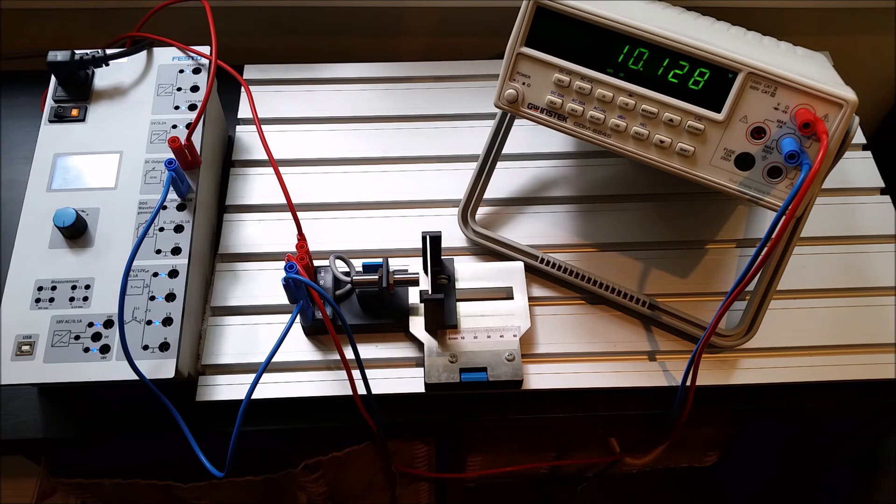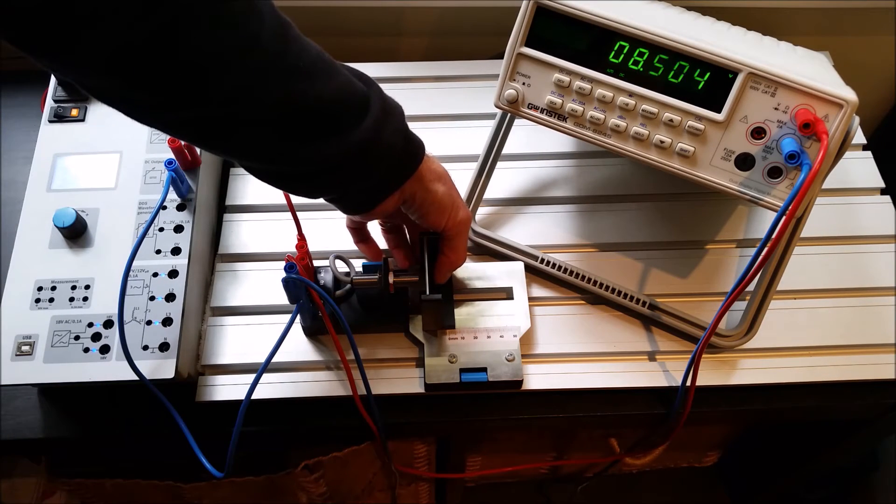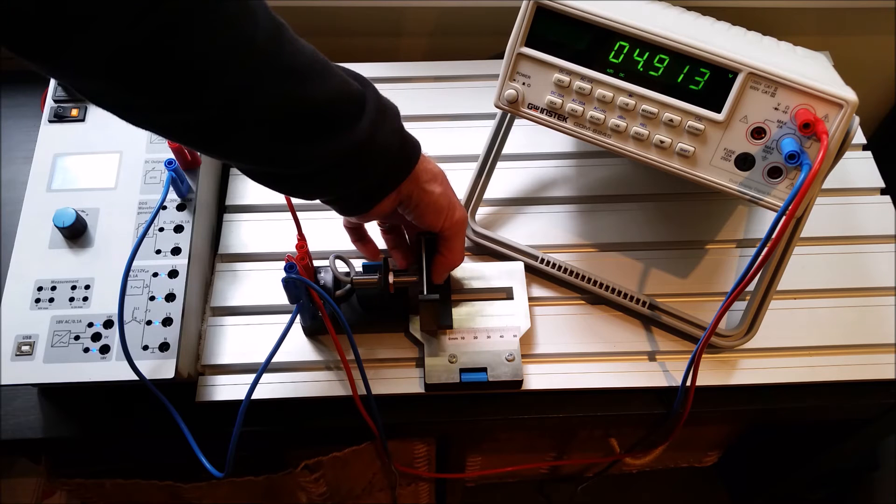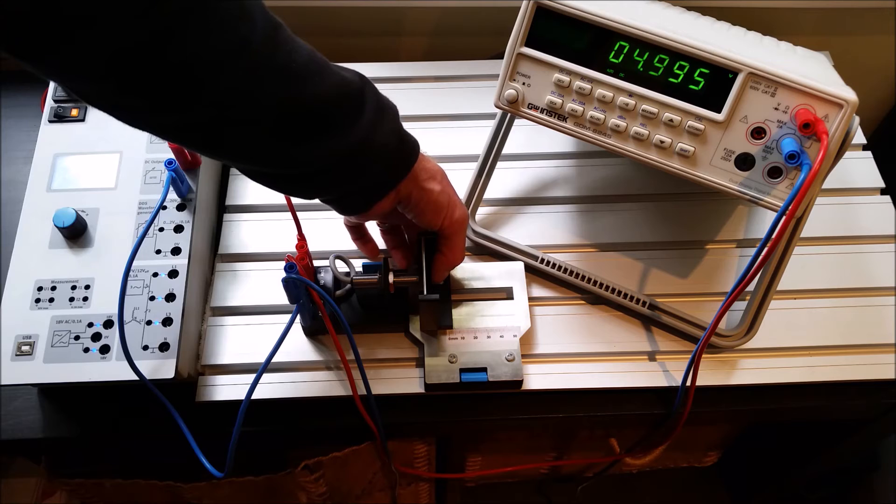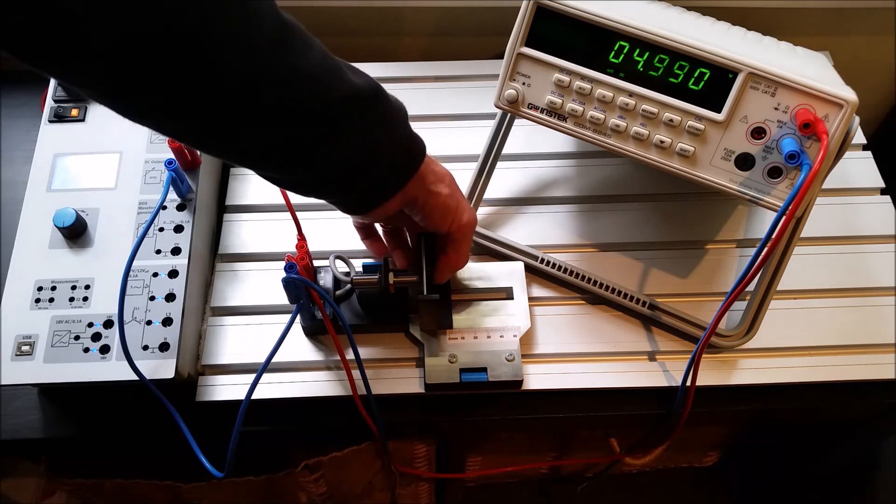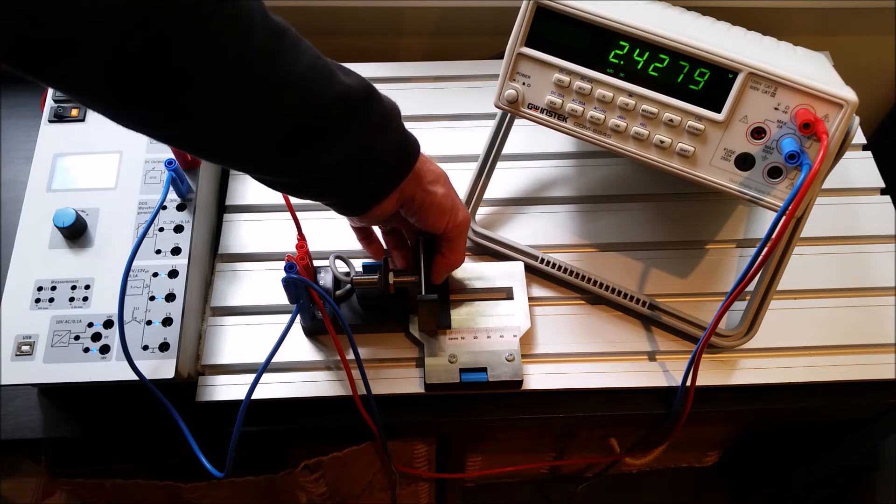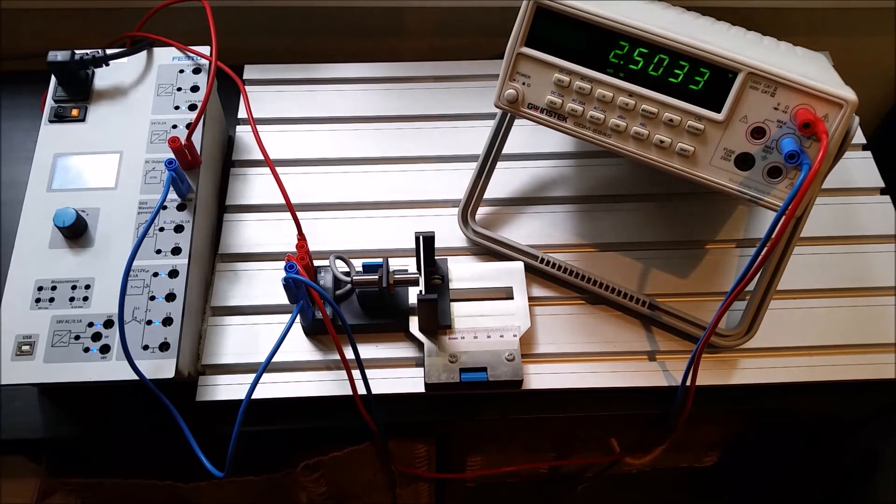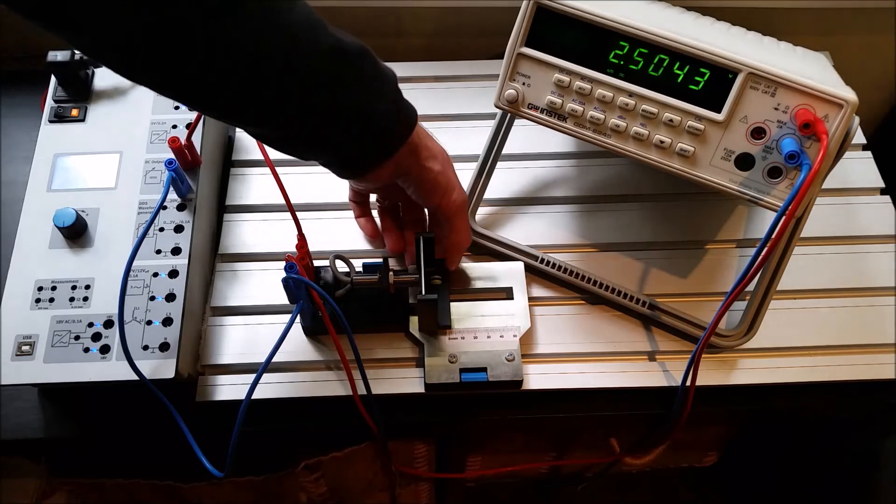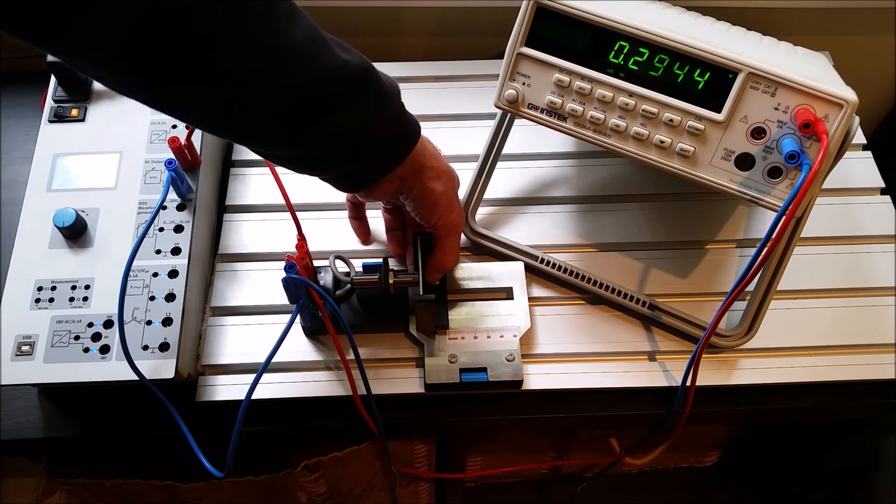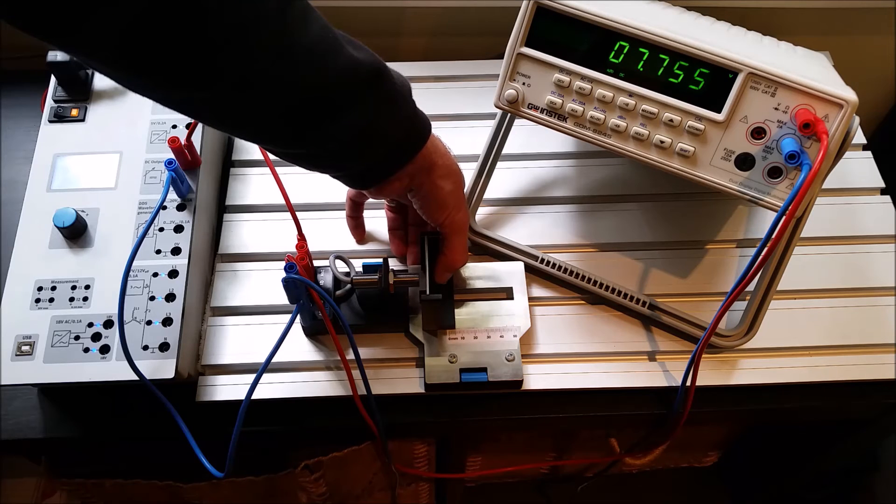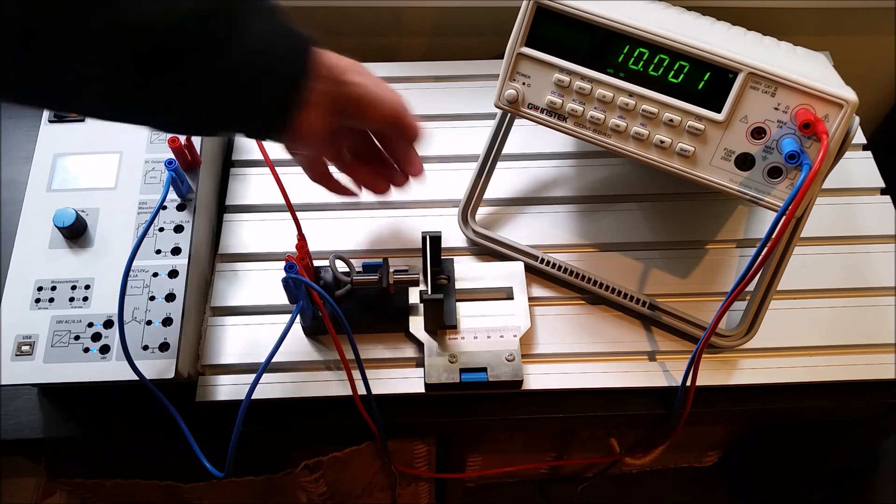And it's a linear output. If I go to 3 mils, let's see if we can get 3 mils here. We should get 5 volts. So come on. There we go. So we've got 5 volts there, and that's roughly about 3 mils. 1.5 mils should give me half of that. It should give me 2.5 volts. So there's 1.5, and I'm getting 2.5 volts.